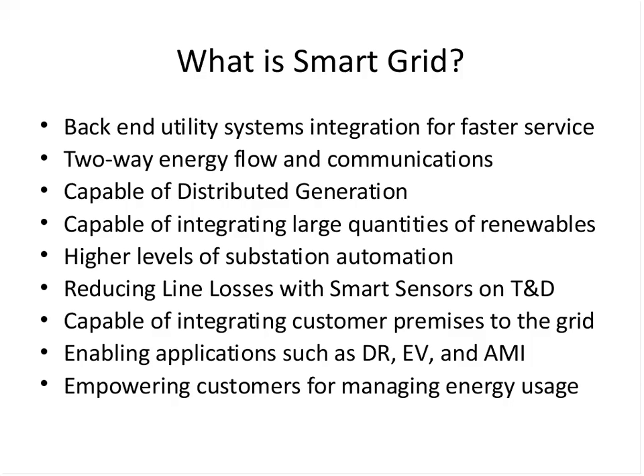Now, if ohmic losses, the loss due to resistance on a wire, is only 1 to 1.25%, what's the other 5 3/4 percent? It's all inefficiencies in the system. Because of lack of awareness of what's happening on the grid, we overcompensate, trying to make the voltage acceptable at the other end. If we had better sensors, if we had information from smart meters fed back into our SCADA systems, we could plan better and control the voltage better at the edge.